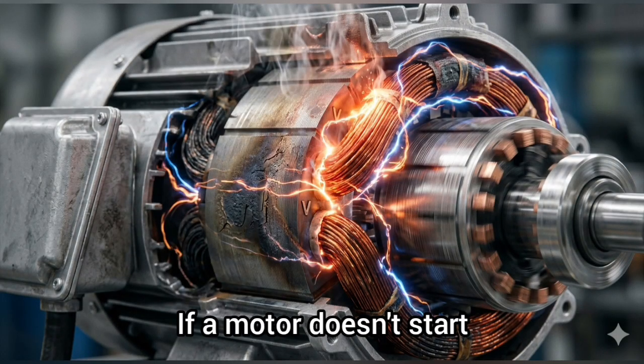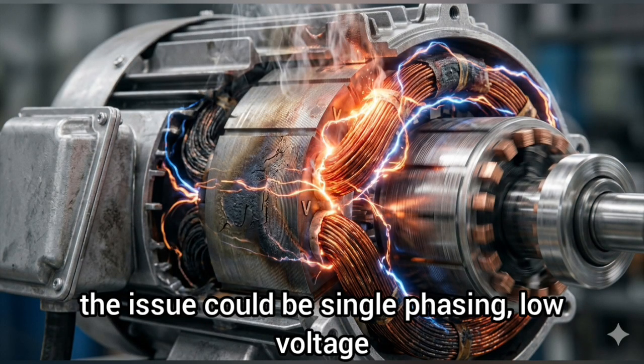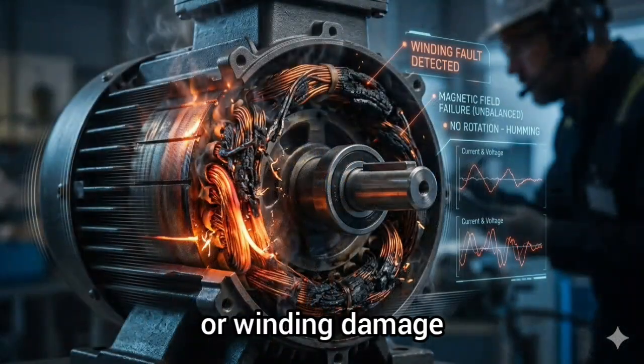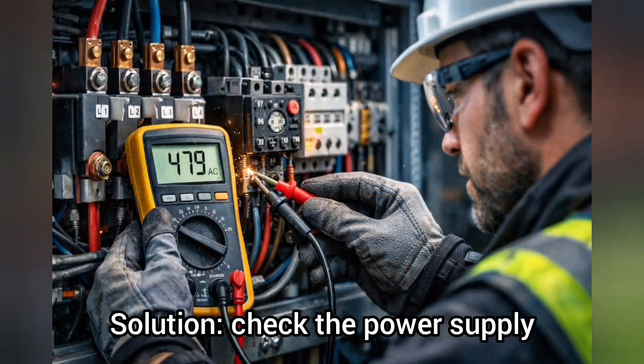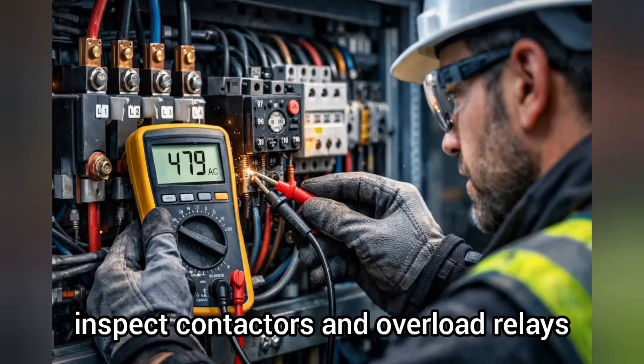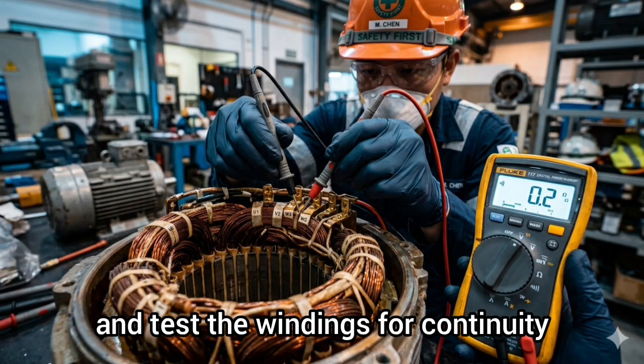2. Failure to start. If a motor doesn't start, the issue could be single phasing, low voltage, faulty starter components, or winding damage. Solution: check the power supply, inspect contactors and overload relays, and test the windings for continuity.